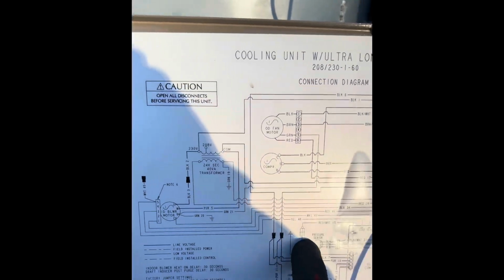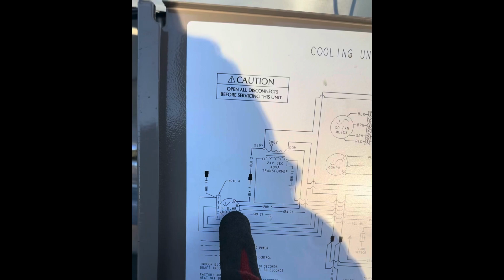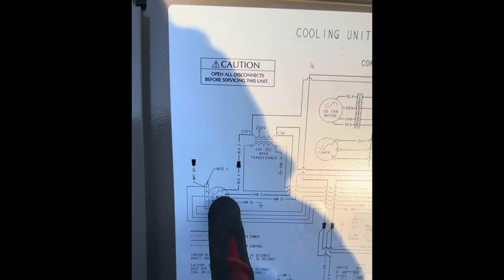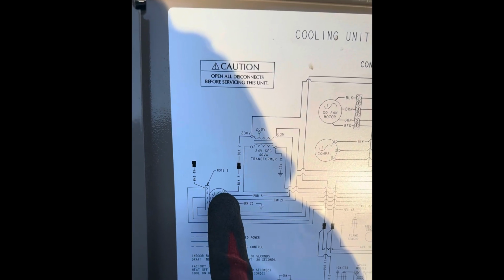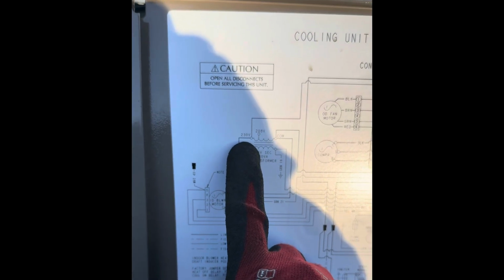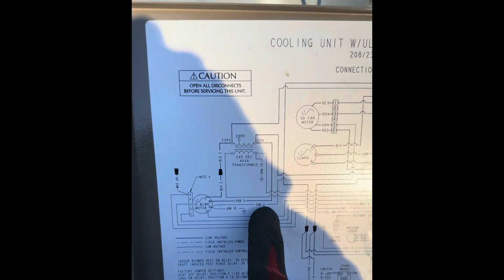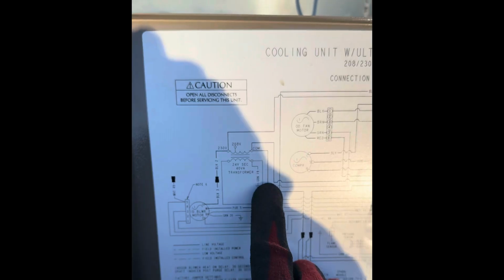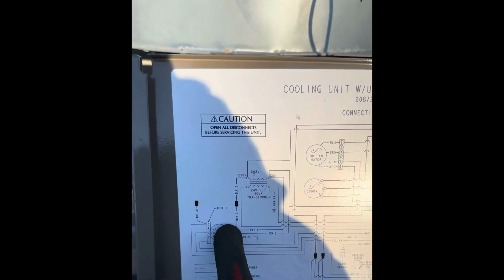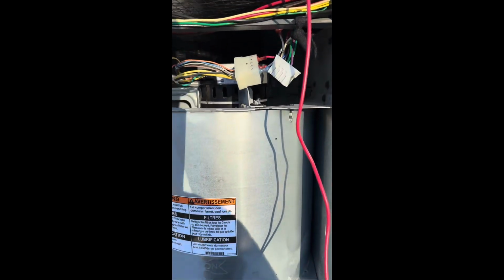So once you verify that you are getting a signal from your control board, the next thing you want to do is check your high voltage side. That's between your line here, so you've got 230 volts coming in, and then you got your neutral coming out on your other side for common. Once you verify that, if you got power and you got signal, you know it's pretty much the ECM that is not working correctly.